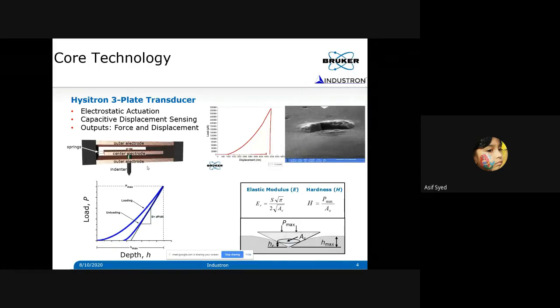That is when you have something like this. I'm showing a transducer over here. You can see there are three plates. The center plate is suspended by a spring, and there are two outer electrodes, and there is a gap between these plates, right? So now if you apply a high voltage at the outer bottom electrode, it is going to generate electrostatic force, and then it will attract the central electrode downwards. And the indenter probe is mounted on the central electrode, and that's how you create force, and that force is applied onto the sample, right?